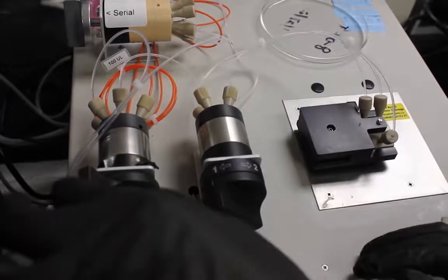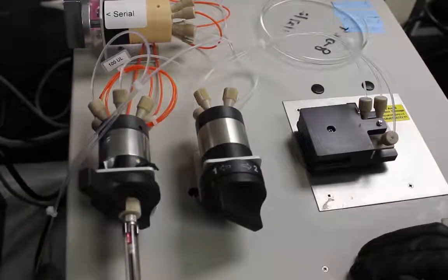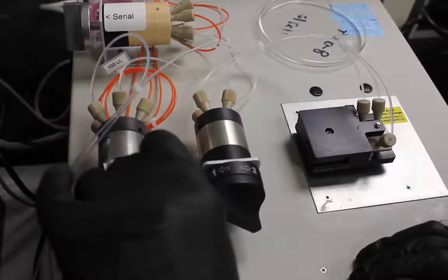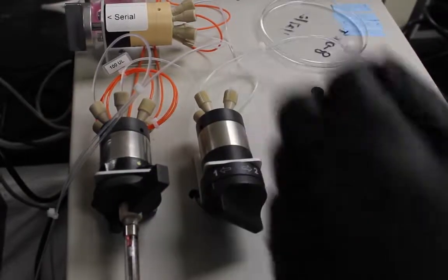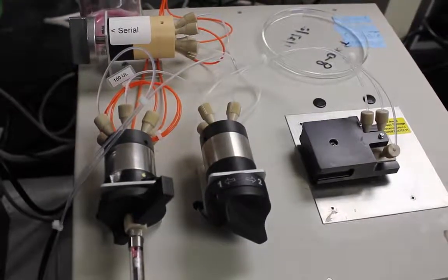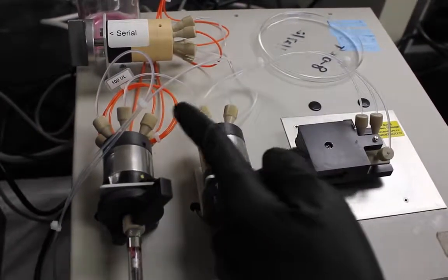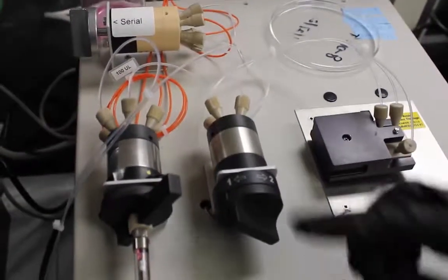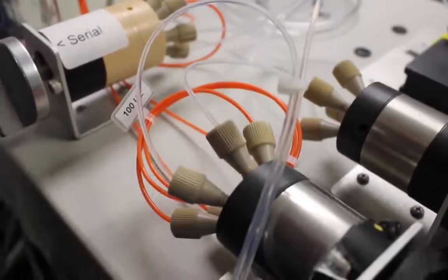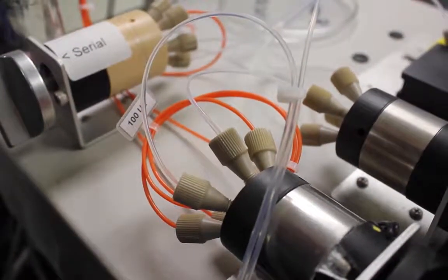Without taking it out, you will switch it. This is in load position right now. You will switch it into injection position, and it's on channel 1 right now, parallel. So it will go through both lines. So you can see if you can track the fluid coming out from here. Hopefully it should be turning red, more or less.